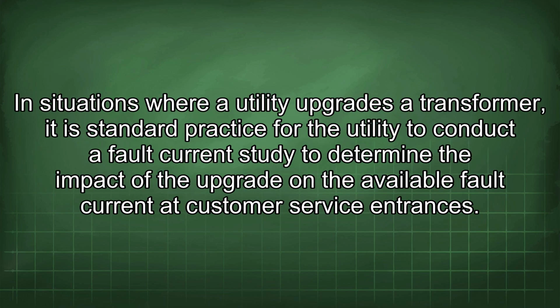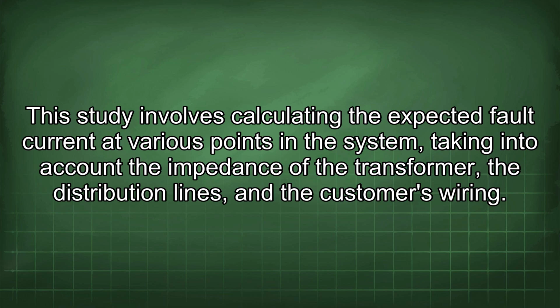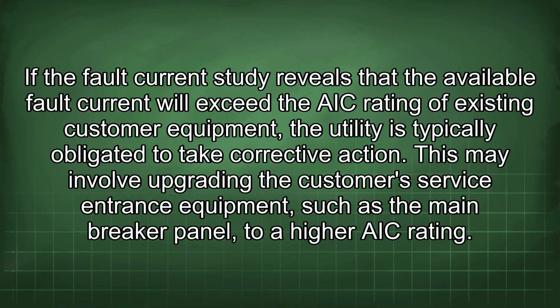In situations where a utility upgrades a transformer, it is standard practice for the utility to conduct a fault current study to determine the impact of the upgrade on the available fault current at customer service entrances. This study involves calculating the expected fault current at various points in the system, taking into account the impedance of the transformer, the distribution lines, and the customer's wiring. If the fault current study reveals that the available fault current will exceed the AIC rating of existing customer equipment, the utility is typically obligated to take corrective action.